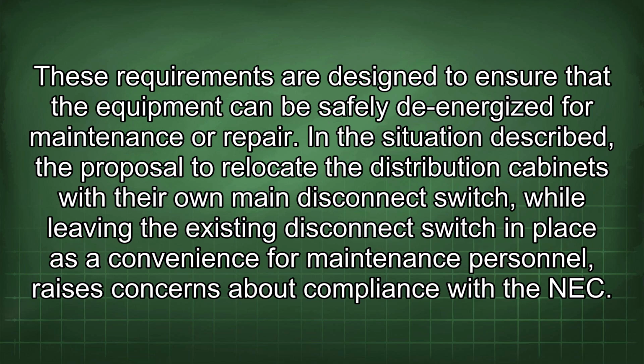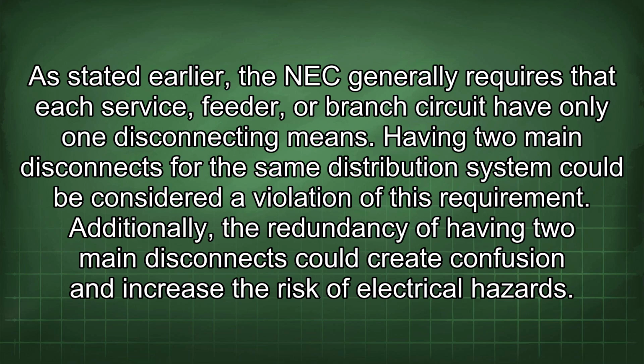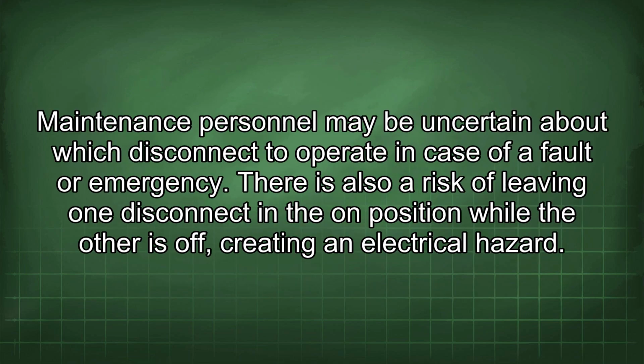In this situation described, the proposal to relocate the distribution cabinets with their own main disconnect switch, while leaving the existing disconnect switch in place as a convenience for maintenance personnel, raises concerns about compliance with the NEC. As stated earlier, the NEC generally requires that each service, feeder, or branch circuit have only one disconnecting means. Having two main disconnects for the same distribution system could be considered a violation of this requirement. Additionally, the redundancy of having two main disconnects could create confusion and increase the risk of electrical hazards. Maintenance personnel may be uncertain about which disconnect to operate in case of a fault or emergency. There is also a risk of leaving one disconnect in the on position while the other is off, creating an electrical hazard.